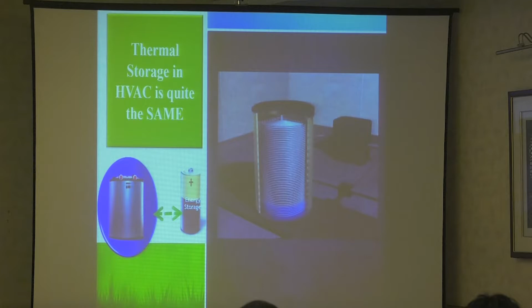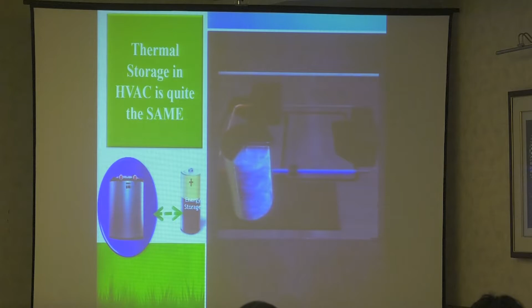Inside each large tank are dozens of spiral tubes, stacked on top of each other. The tanks are also filled with water. At night, coolant from the chillers is pumped through the tubes, freezing the water solid in the container. During the day, warm coolant is pumped back through the tubes, drawing cold from the ice and chilling the coolant. The chilled coolant then goes to air handling units to cool the air. Although off-peak cooling is already being used in many buildings throughout the world, the One Bryant Park building is several years from completion.